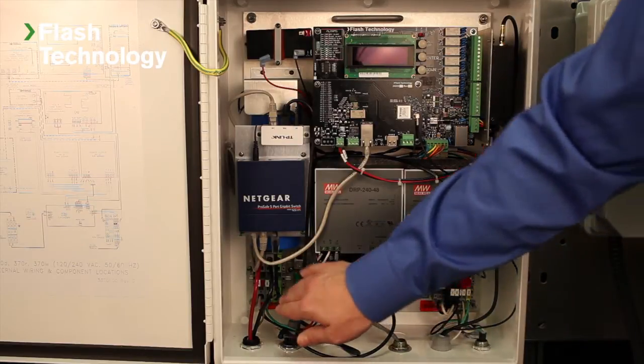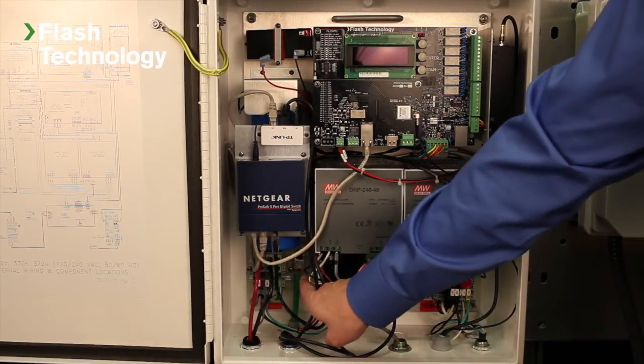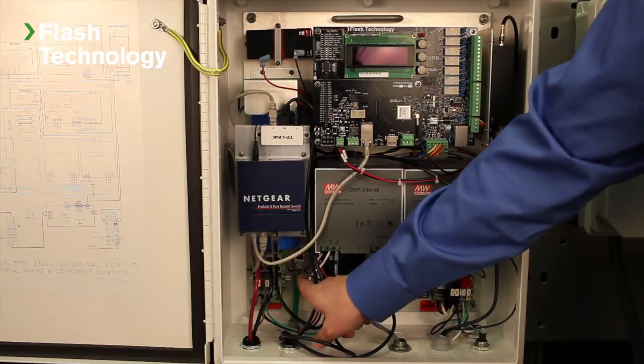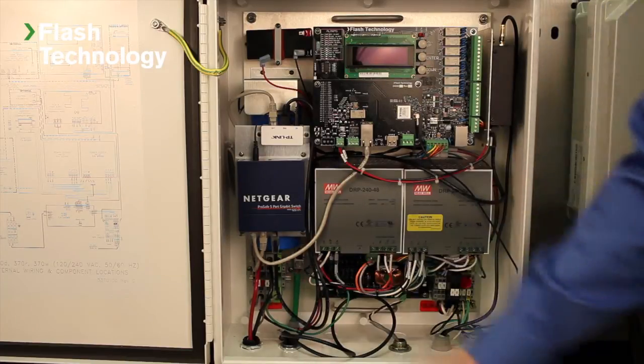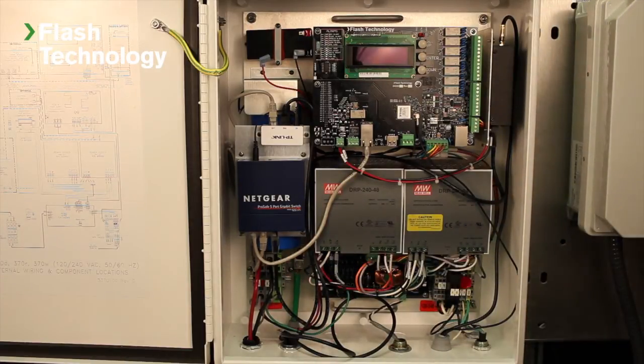Next, we take a look at our system controller grounding. You'll find a number 2 gauge lug pre-installed on the controller. We need to connect that with a number 2 gauge wire. Don't forget to coat both terminal ends with an anti-corrosive agent, something like a Noalox or a copper shield.